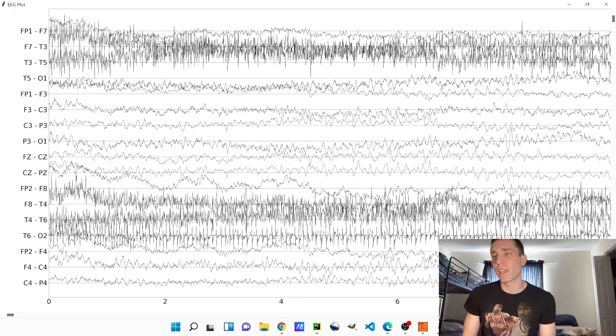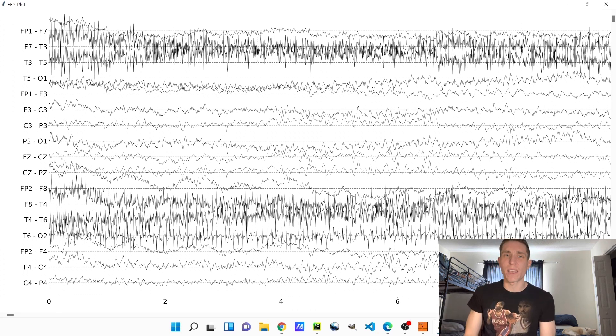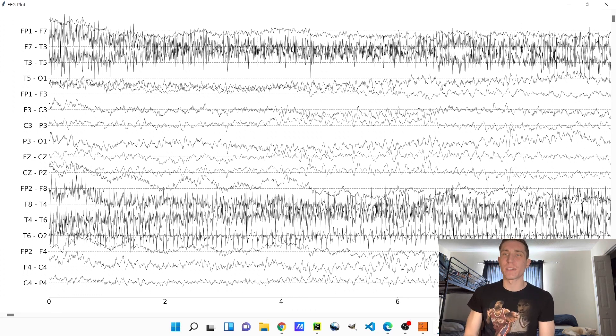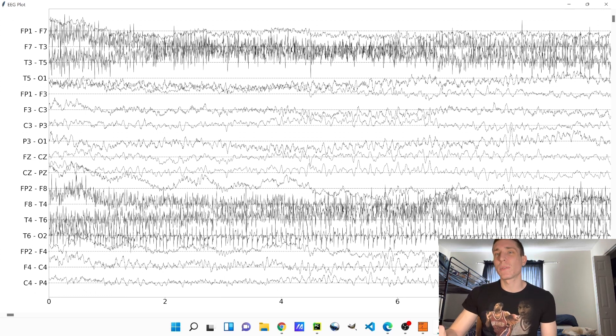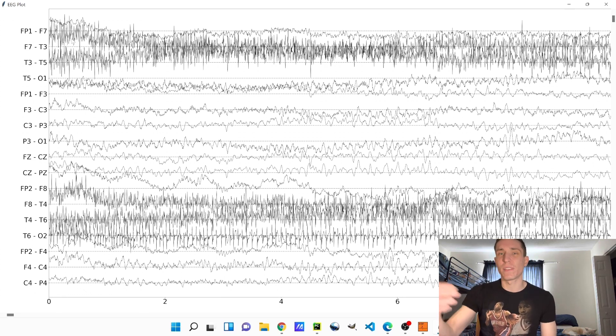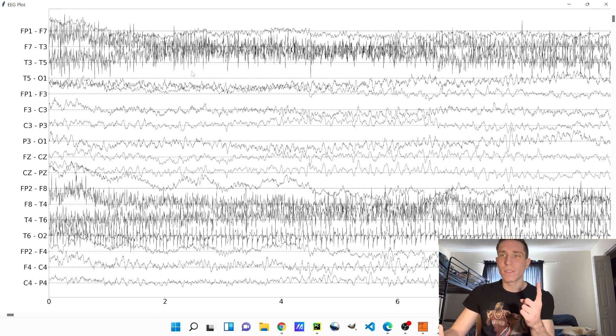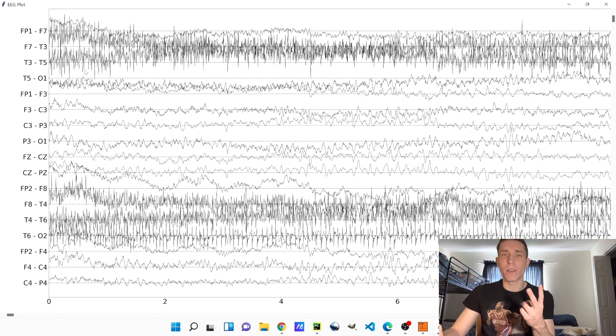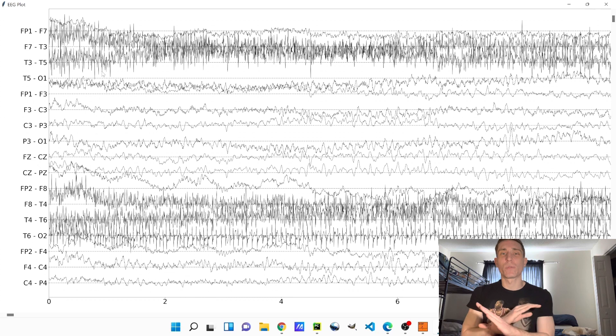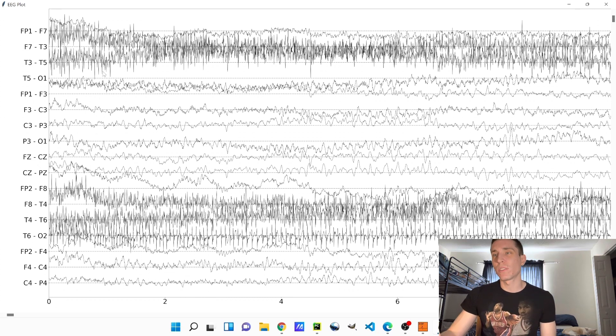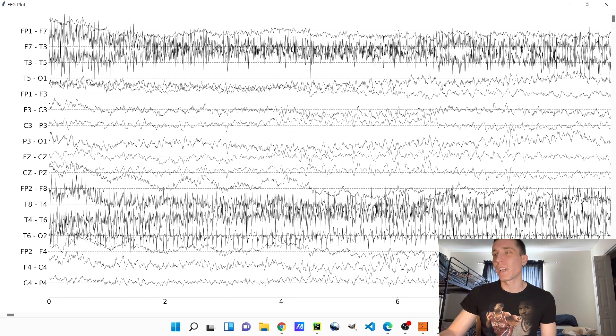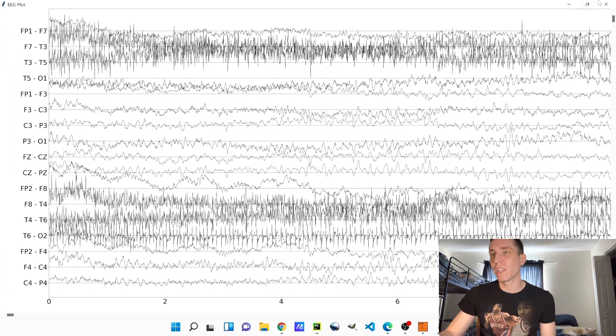Now you might be thinking, well Jared, why don't you just use a high frequency filter? Well, if you use a high frequency filter because yes muscle activity is very high frequency, you're going to filter out the muscle activity, but you're also going to filter out actual brain activity which we don't want to do. So in order to do that we use our special muscle artifact reduction filter right here.